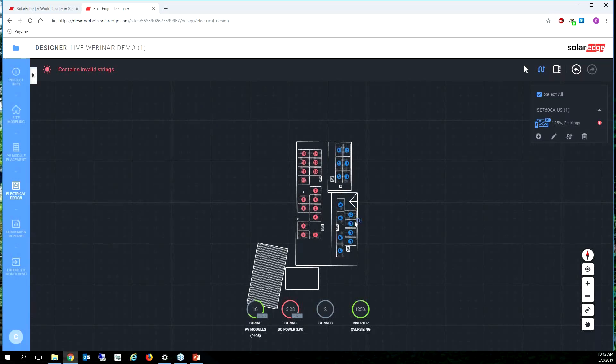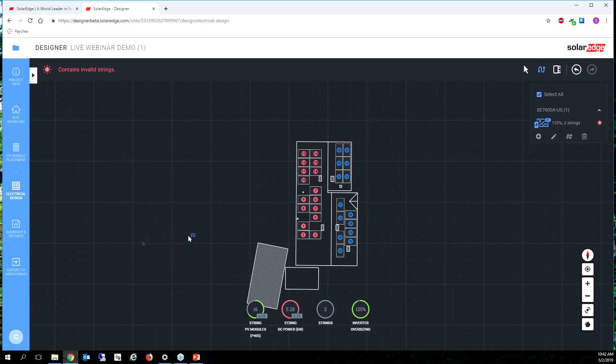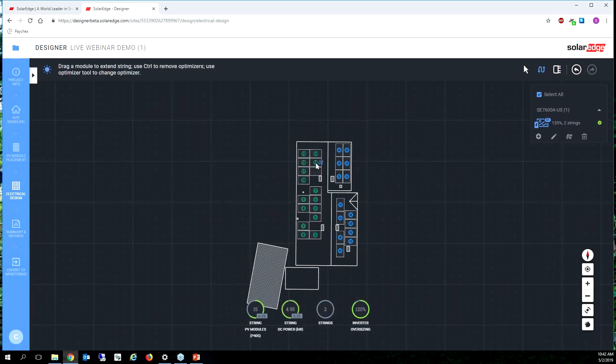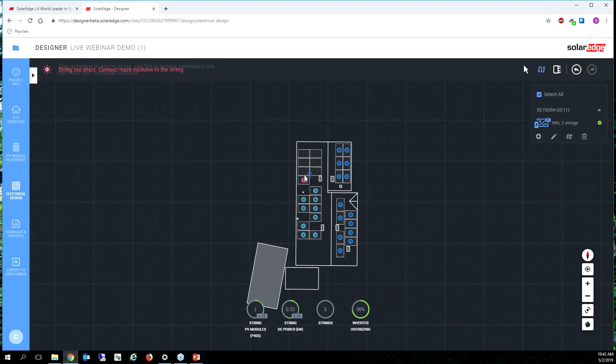Ah, we got to 16 so the maximum string length for the storage inverter using these solar panels is going to be 16 modules because the maximum string wattage is 5250 and we're at 5280. Oh man, 30 watts, that 30 watts killed us. So let's undo this one and we're going to actually maybe three strings is the best solution.